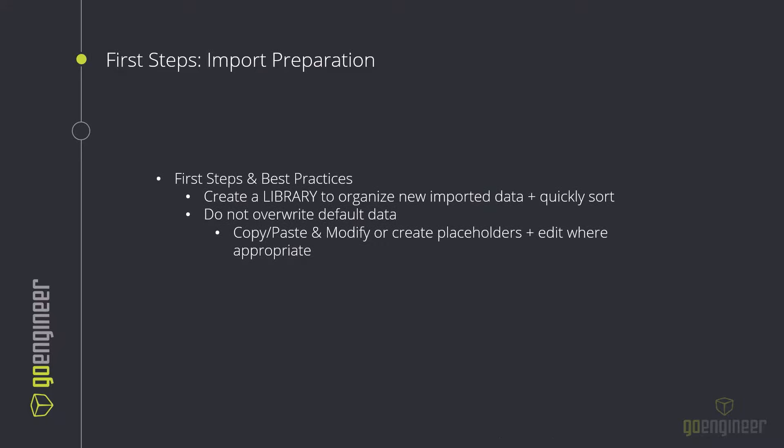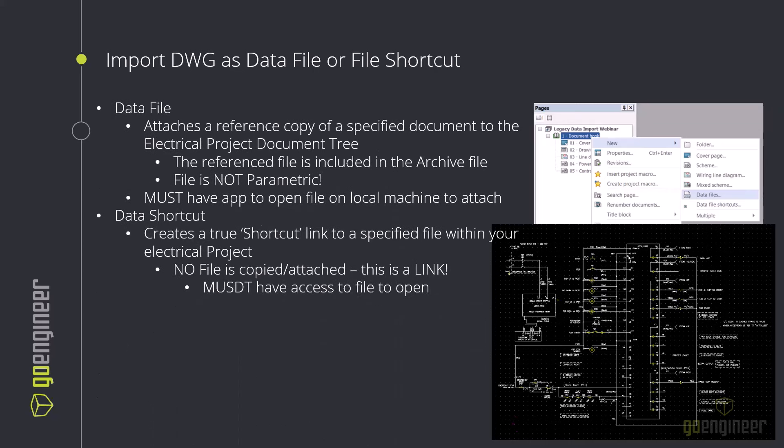The first thing we'll look at is importing a DWG as a data file or a file shortcut. A data file attaches a reference copy of a specified document to the electrical project document tree. When you archive your project, that file is extracted out and included within the archive — so it copies it at the moment you attach it and also loads it into the archive you send to other users. One caveat: you need an application on your machine capable of opening that file type.